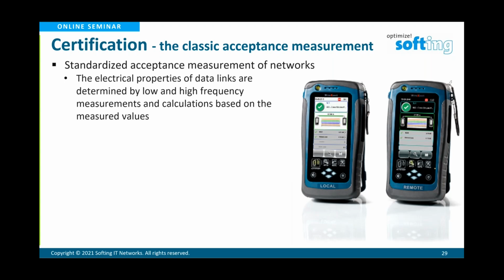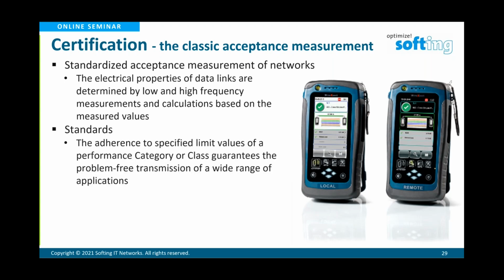But larger installations usually test against the electrical properties of a data link. These are determined by low and high frequency measurements, plus some calculations based on the measured values. The standards today have limits for the specific categories or classes, and if you fulfill this performance from the category or class, it guarantees problem-free transmission for a wide range of applications.